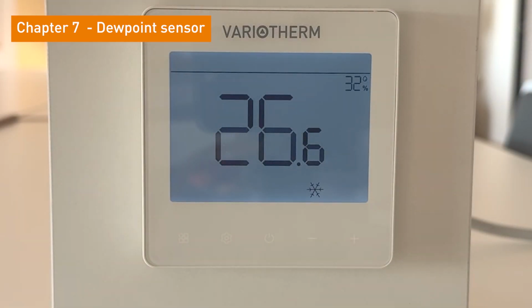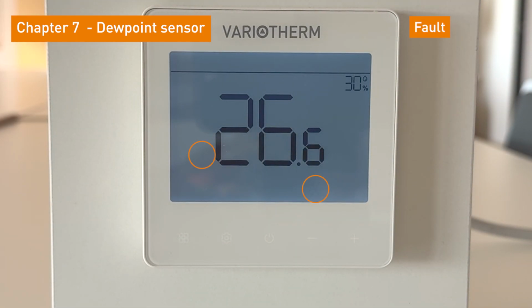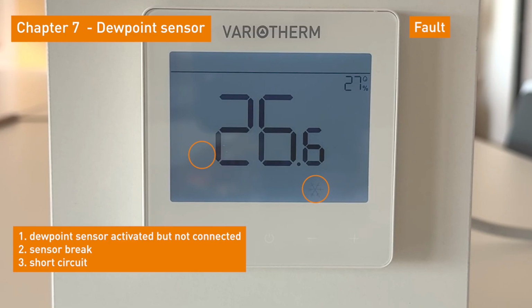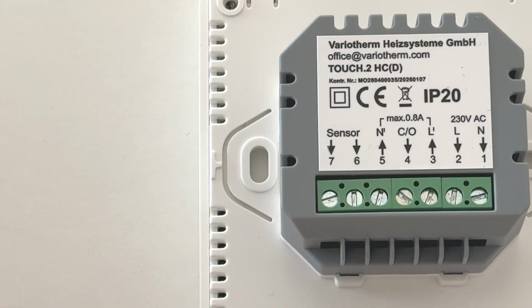If the status is fault, the output is turned off, the cooling on symbol disappears, and the cooling mode symbol flashes. Sources of error are: the dew point sensor is activated but not connected, sensor break, short circuit.